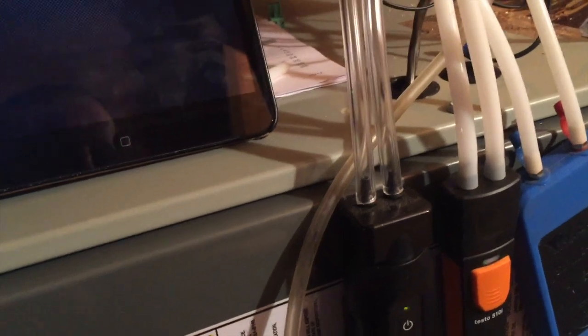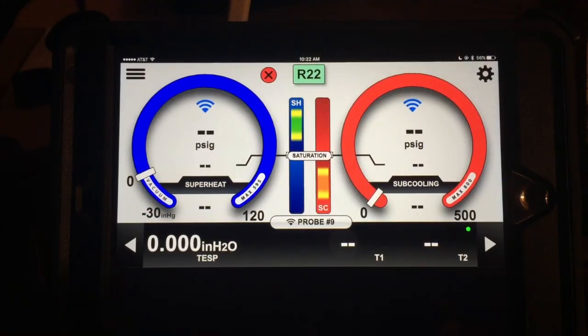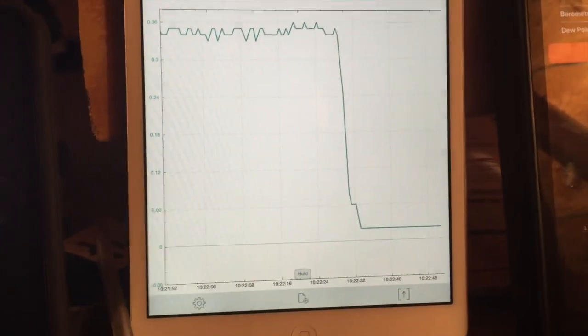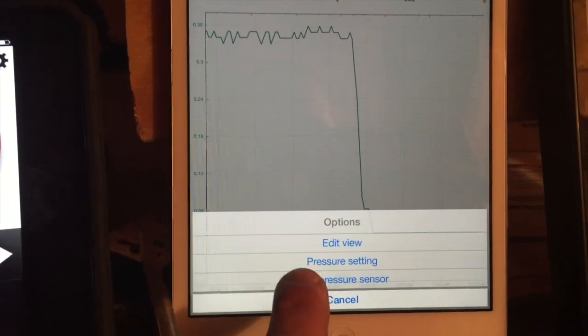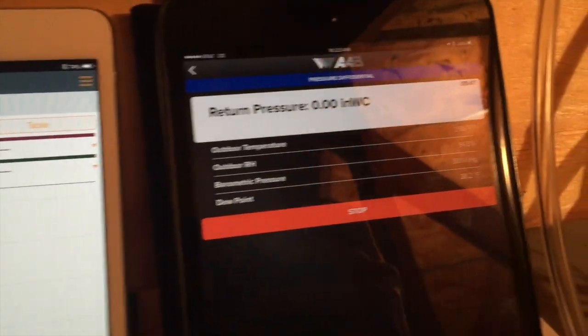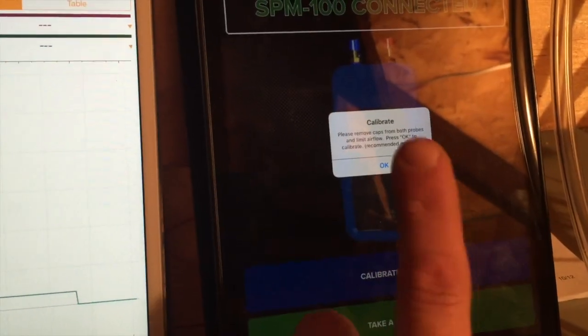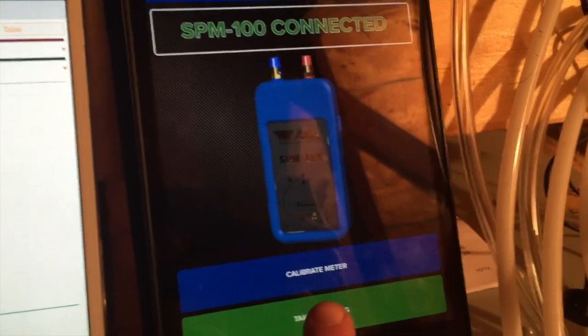I'm going to make sure that everything is zeroed. We'll disconnect the hoses and then reconnect and show you what everything looks like. The I-manifold is zeroed out. The Testo 510 is reading 0.02, so I'm going to go ahead and zero that measurement out. This one is reading zero also, but we're going to stop that, delete that, and calibrate the meter.